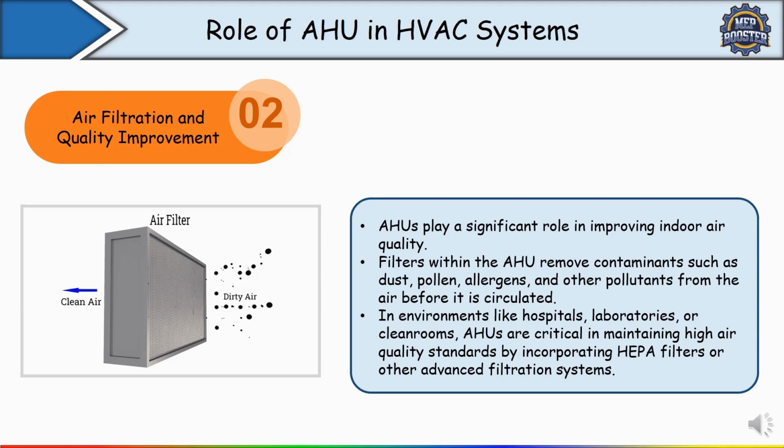If I take one example, all of you know that in hospitals generally AHUs are equipped with a HEPA filter, meaning high efficiency particulate air filter, to remove harmful contaminants, protecting patients from airborne infections. So the air circulated in operating rooms and patient wards is cleaner and healthier as a result. HEPA filter can filter the air up to 99.97%. So that is why in hospitals generally we are using HEPA filters.